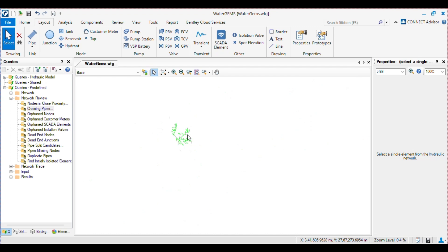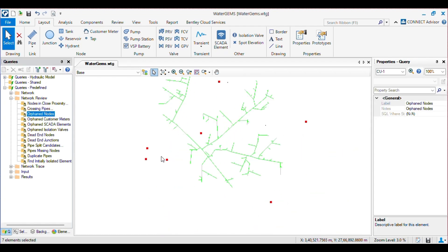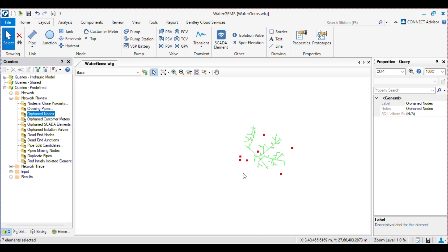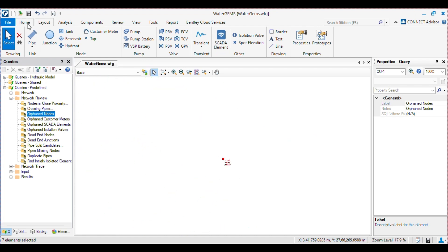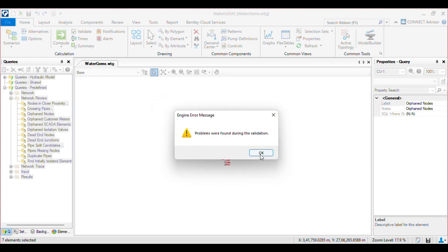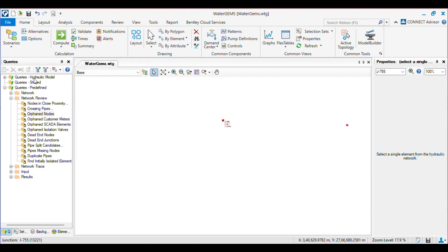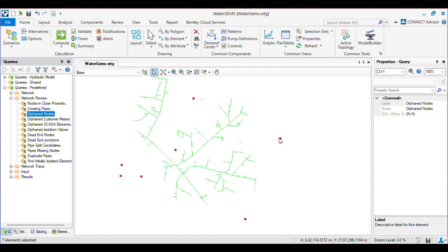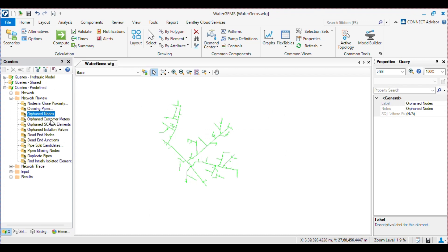Then we have Orphan Nodes — it will select all the nodes which are not connected to the network. Click on that and you will get the orphan nodes. Sometimes you make the network and delete some pipes but the junctions are not deleted, so when you validate you will get queries saying the node is not connected. By using this query you can identify all the orphan nodes in seconds, click on them, and delete them.